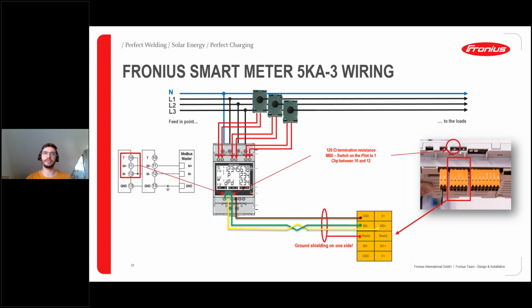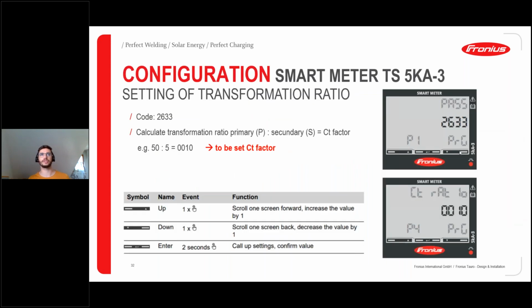Yeah, the next step is, of course, to set the current transformation ratio, because the ratio depends on the type of current transducers you're using. And the ratio can be set as follows. We need to go on the display on the smart meter to page 1. So we have up and down buttons, and in the middle we have an enter button. And we need to go to page 1 and type in the password 2633. That's always the same password on every Fronius smart meter.